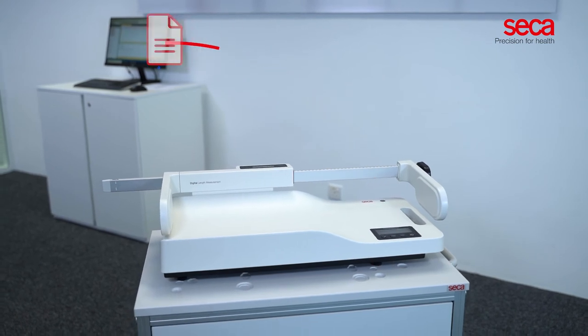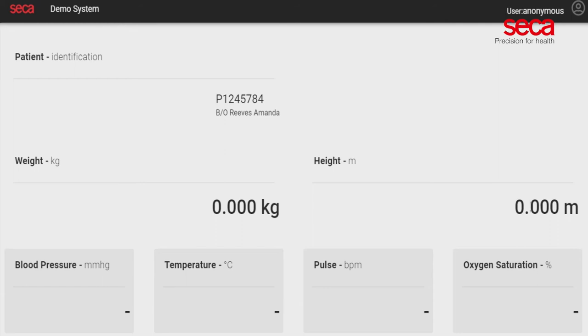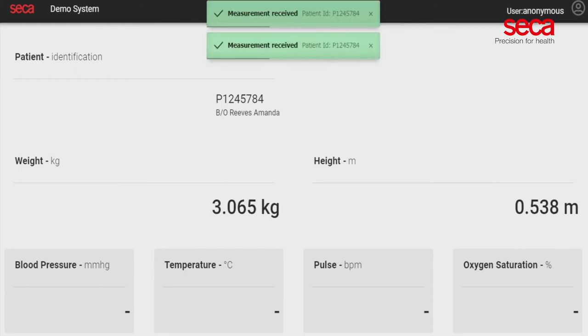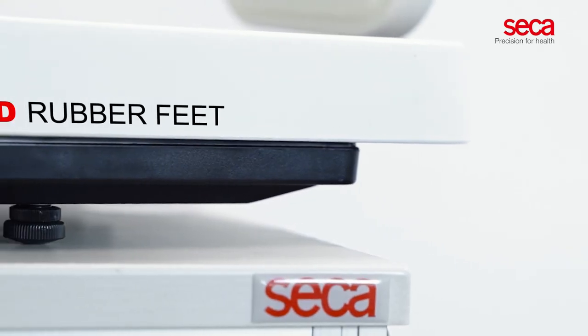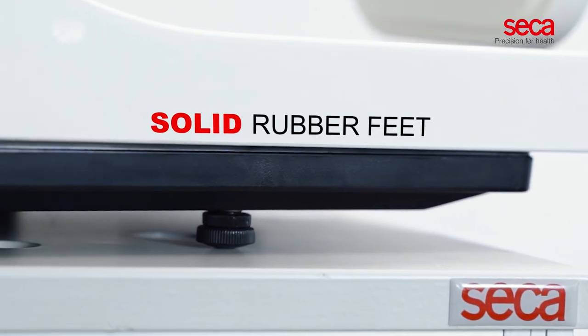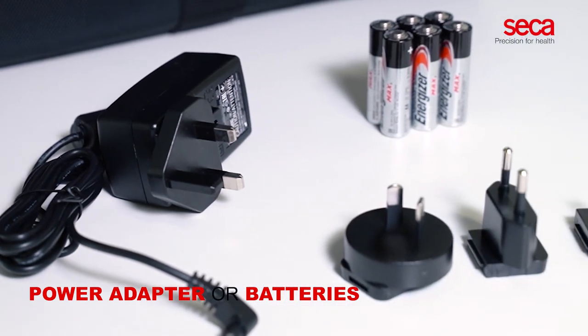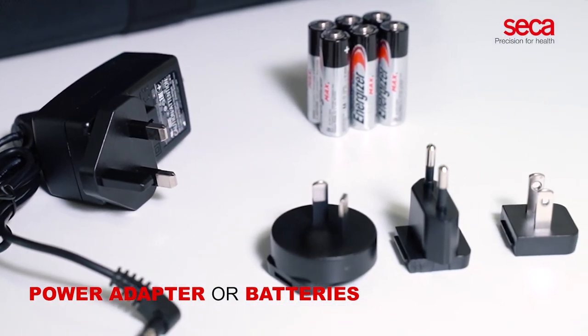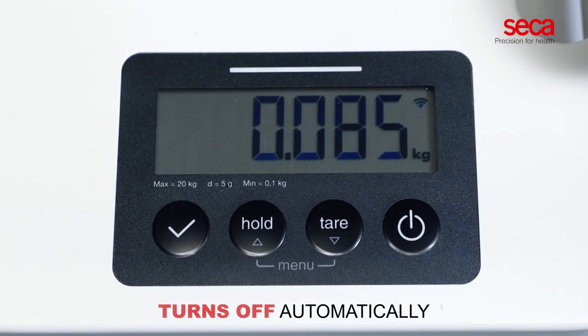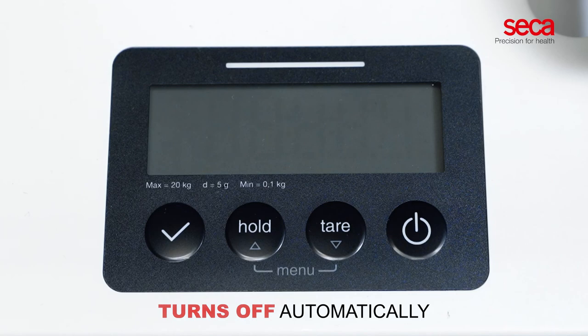seca 333i allows data to be sent directly to any electronic medical record to avoid manual transcription errors. The solid rubber feet of the weighing scale ensure a firm stand on any surface. seca 333i can be operated with either a power adapter or batteries. To ensure a long battery life, seca 333i turns off automatically when not in use.